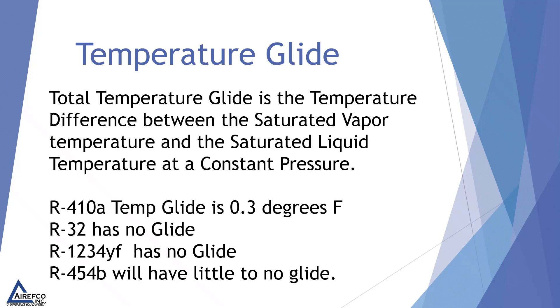R410A has a temperature glide of 0.3 degrees Fahrenheit. R32 has no glide and R1234YF has no glide — and these are the two refrigerants that make up R454B. Therefore, R454B will have little to no glide.